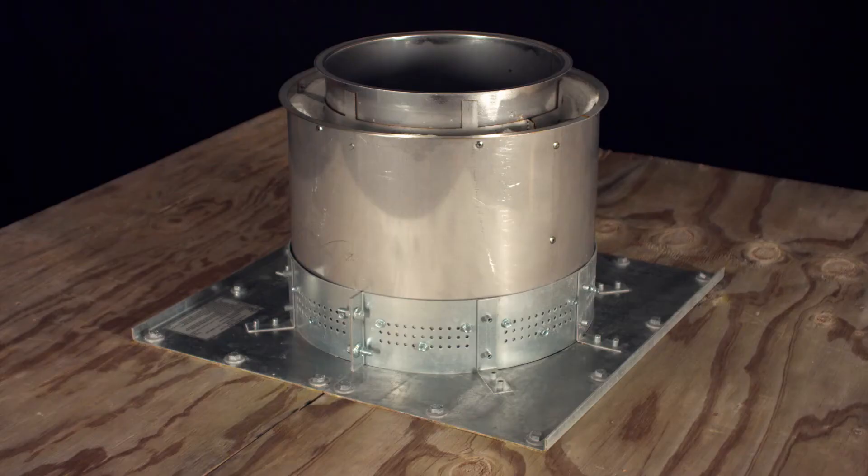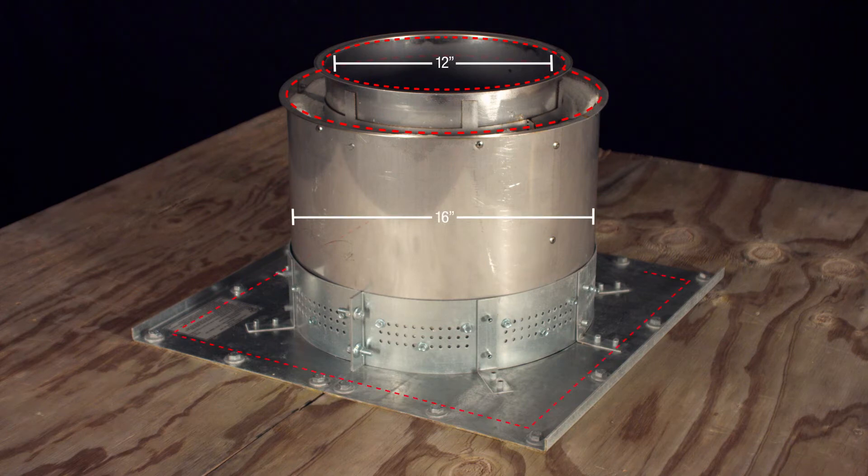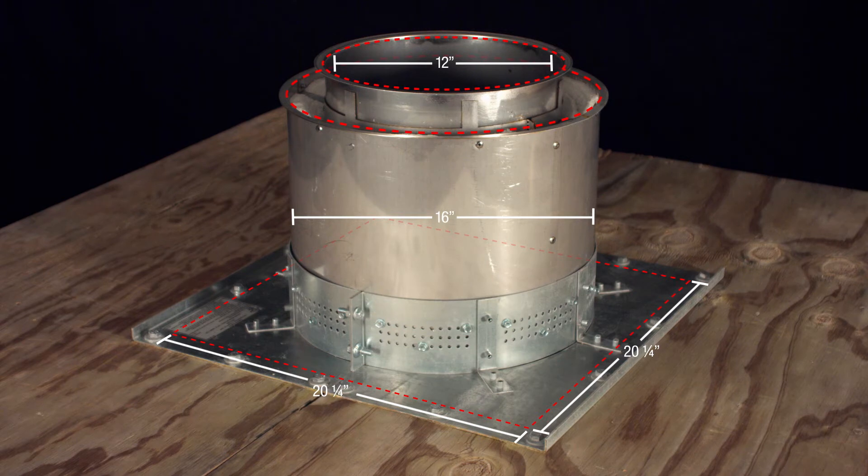For example, the duct shown here has an inner diameter of 12 inches and an outer diameter of 16 inches, so the opening in the floor is a 20 and a quarter inch square. The additional quarter inch ensures the opening meets the required minimums.